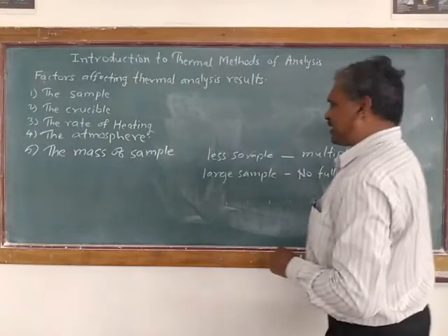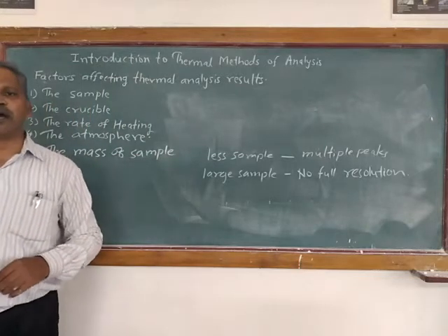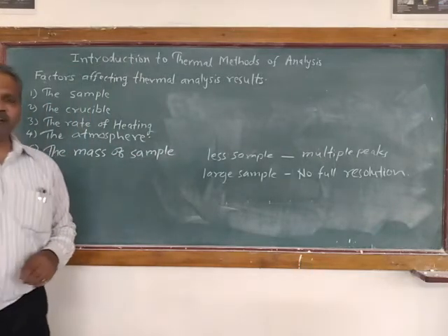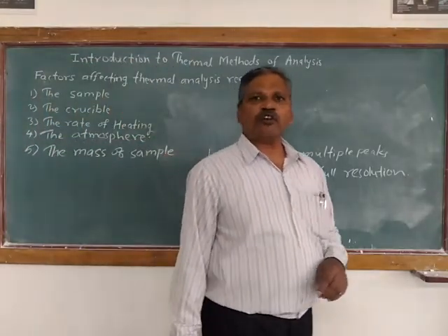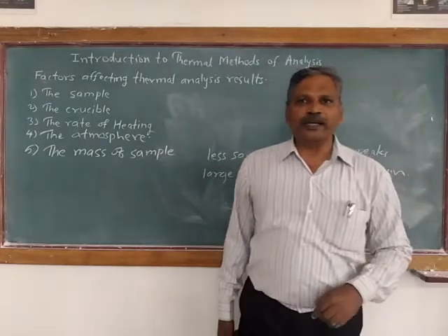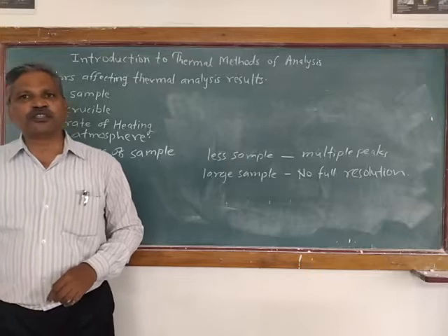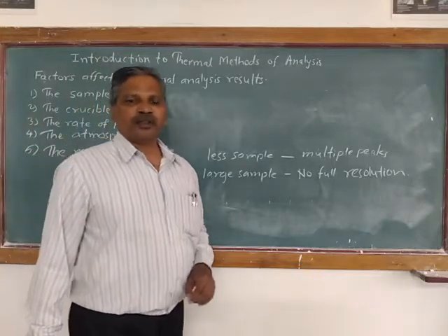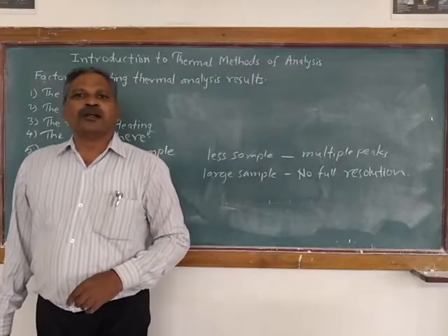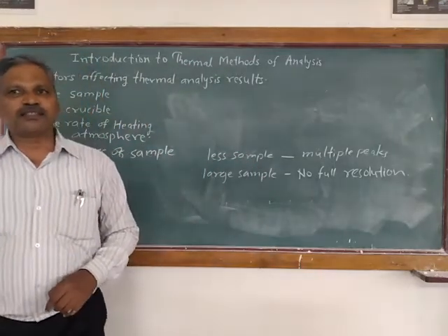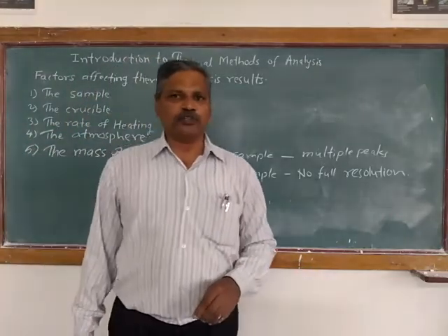So sample size should not be too low, and it should not be too high. When we wish to analyze mixtures in which small amounts of one component need to be detected, for example, a coating on the filler used in a plastic formulation, then in that case, very large samples may be required. Comparison of the thermal analysis curves should be done only when comparable sample masses are used.